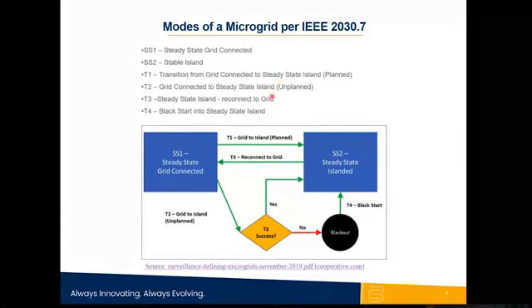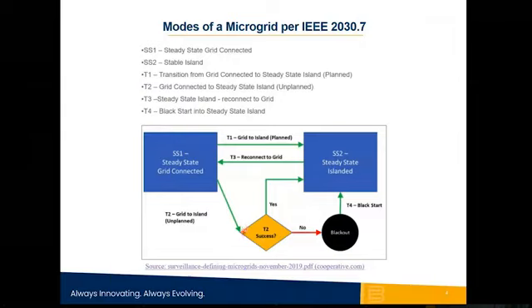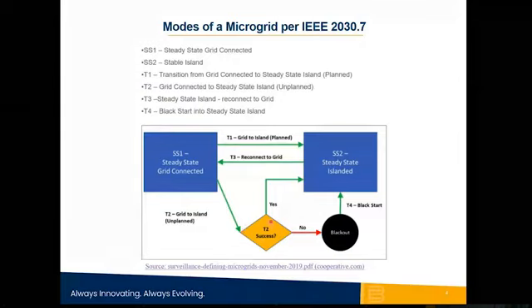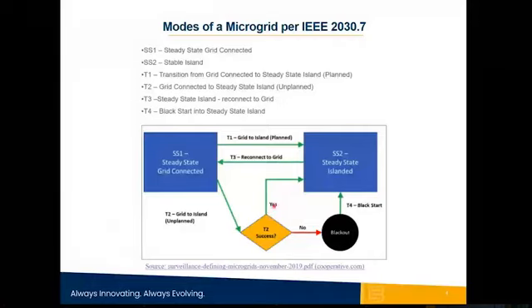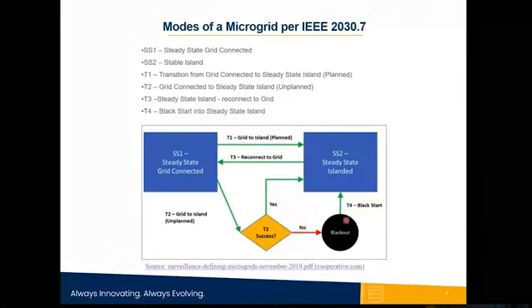But what if the generators were not available? For example, the controller was not left in automatic mode and the generator didn't start because it received a remote start and now it's not in auto and didn't start. Then you have a blackout period. So an unsuccessful transition would result in a blackout period, and then you would come from a black start state to a steady state island state.